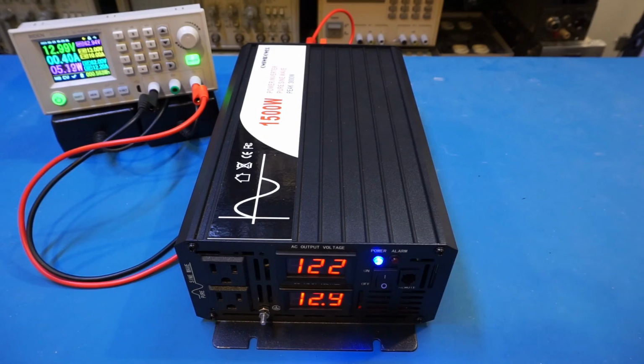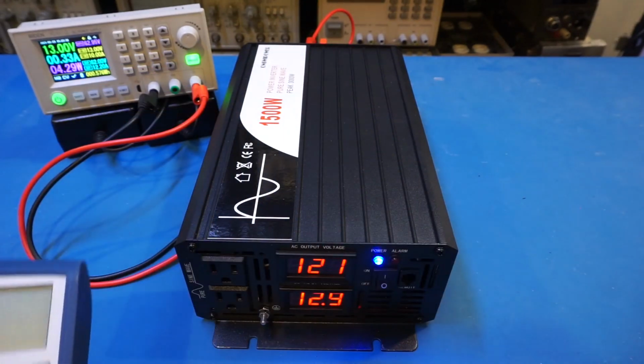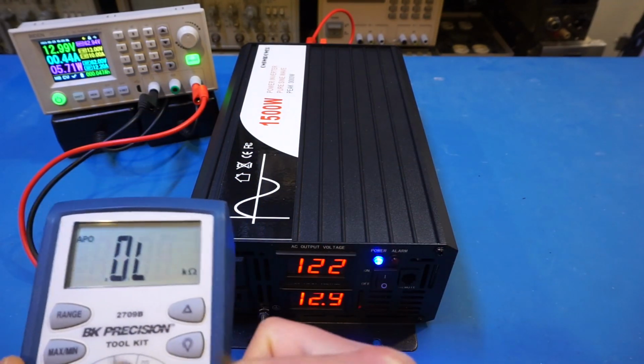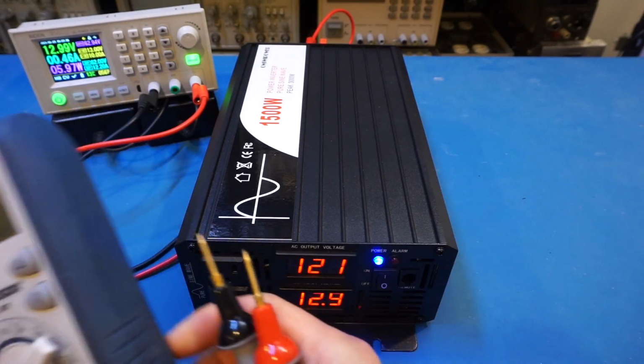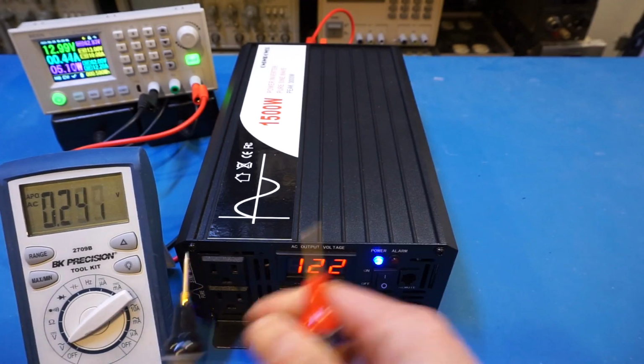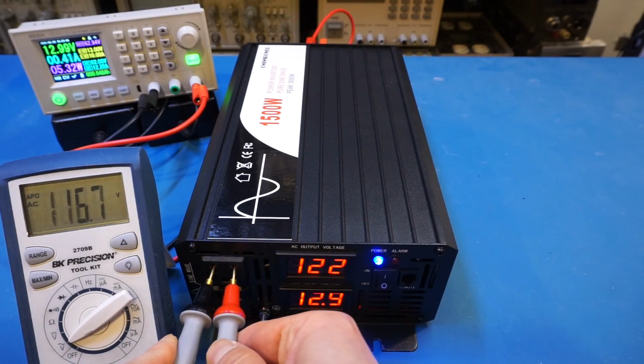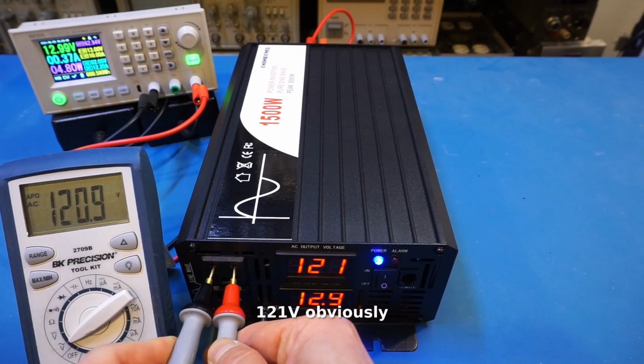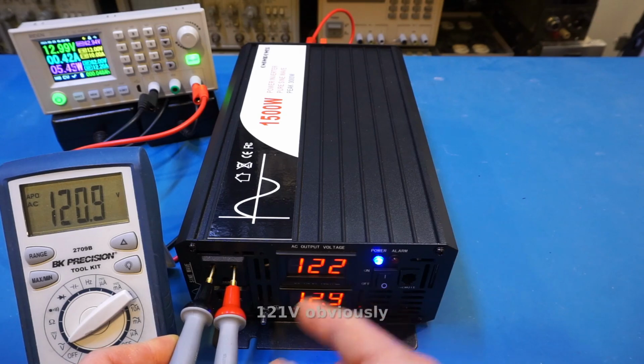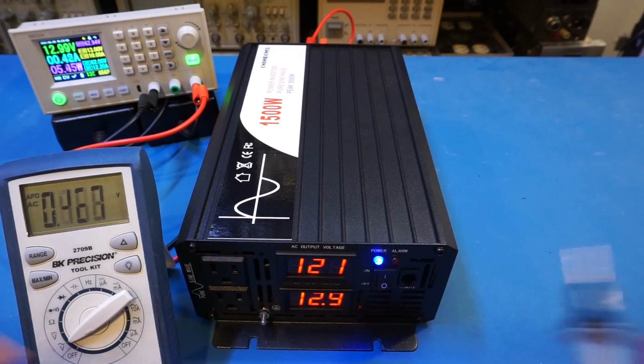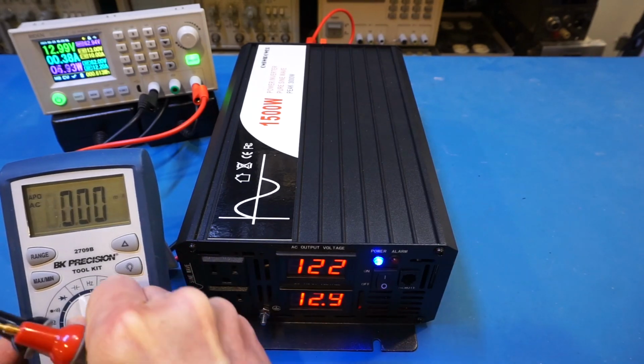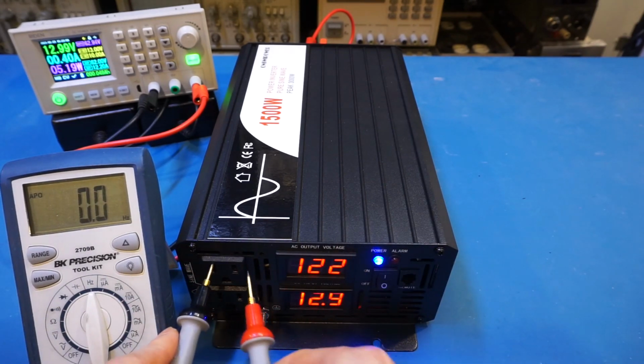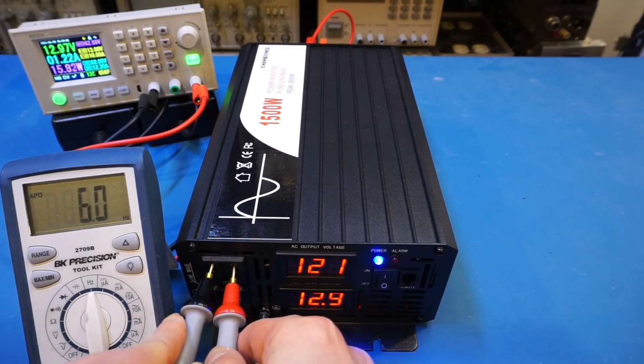So that's really good. Of course, we wanted to measure the output voltage accuracy and output frequency, and I have no doubt those will be right on spec as well. Let's take a quick look. So it's 121 volts, which largely agrees with what the meter says. Now let's check the frequency—it's 59.7 Hertz, so that's close enough.